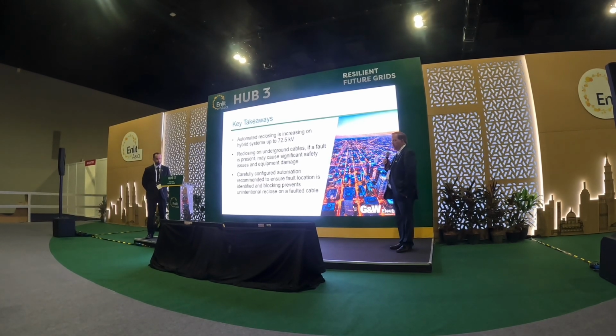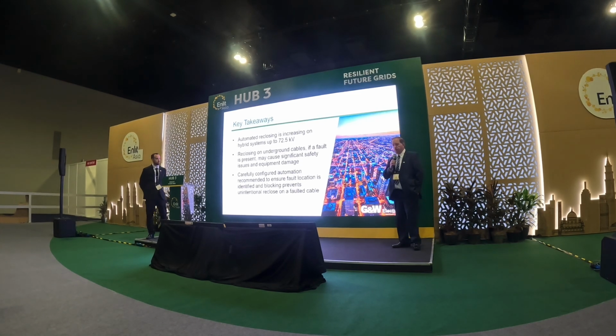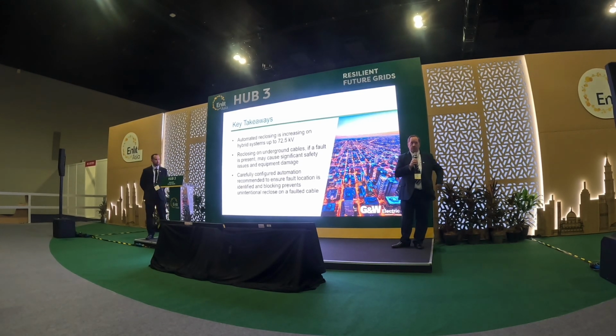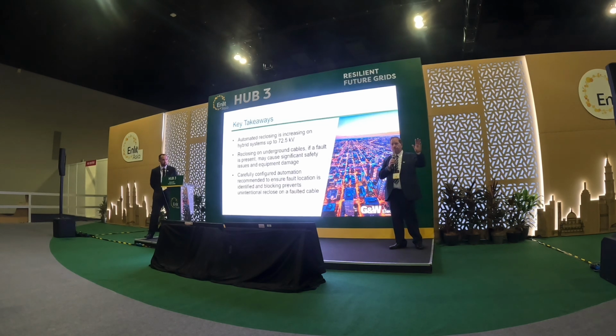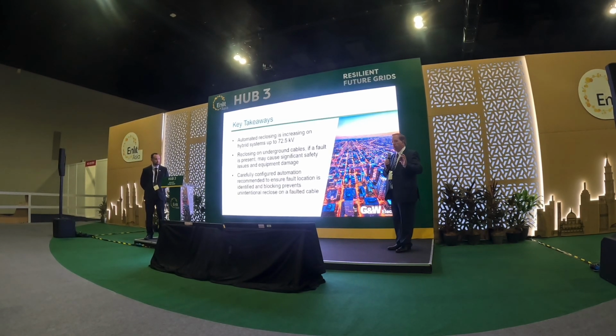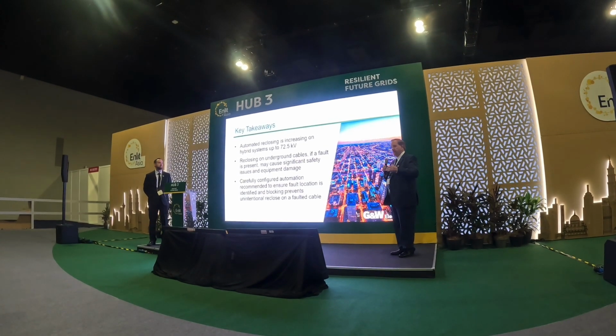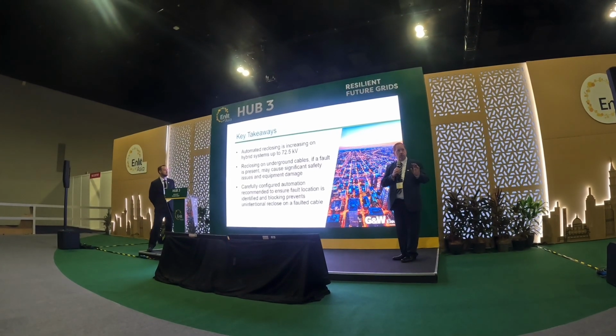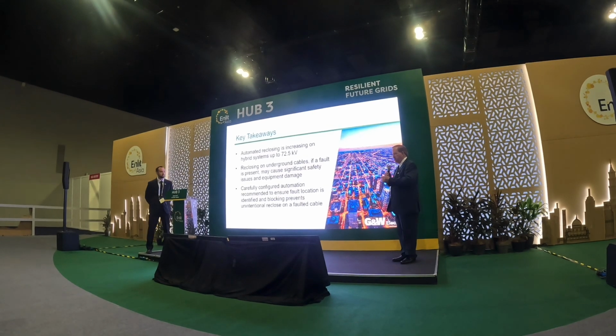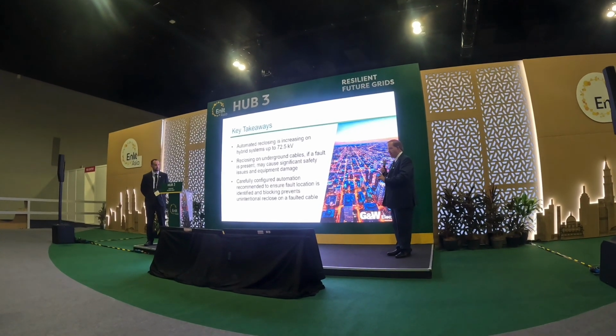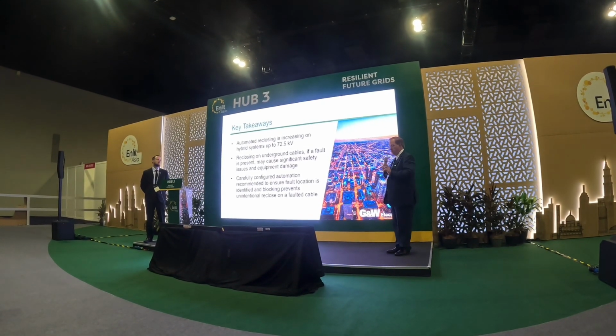So that's why I wanted to give you this cautionary tale. Do not reclose on underground. Do not be afraid to put up reclosers, and if you have them, use them, but do not reclose on underground. Make sure you work with your technology providers, get the advice, make sure you have the automation, the blocking schemes, the detection methodologies, know where the fault is before you reclose, and then you can do so safely.